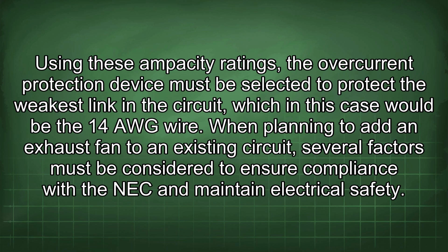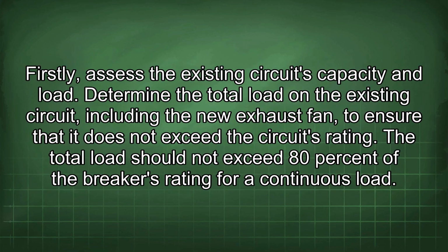When planning to add an exhaust fan to an existing circuit, several factors must be considered to ensure compliance with the NEC and maintain electrical safety. Firstly, assess the existing circuit's capacity and load. Determine the total load in the existing circuit, including the new exhaust fan, to ensure that it does not exceed the circuit's rating. The total load should not exceed 80% of the breaker's rating for a continuous load.